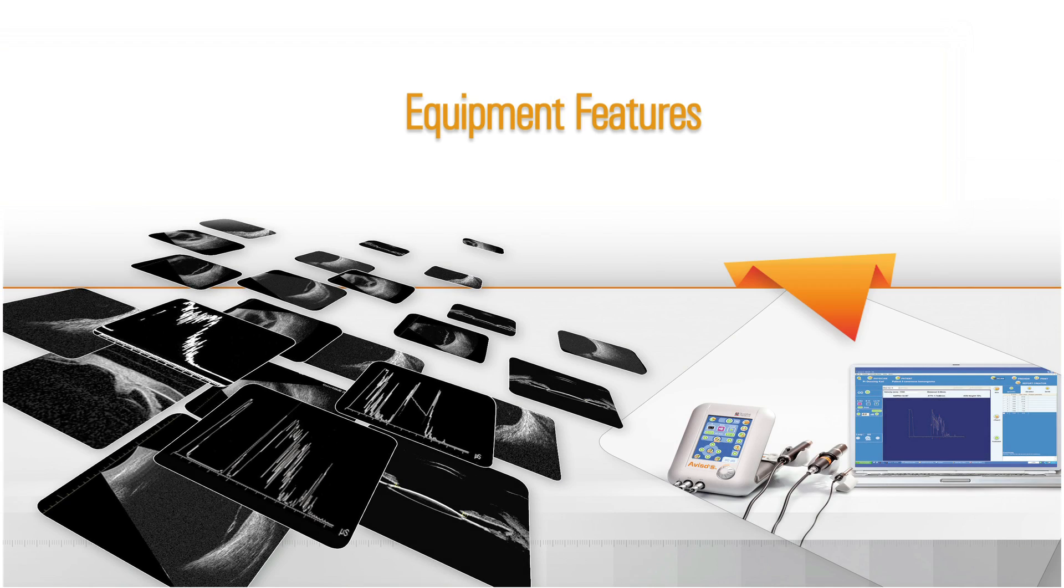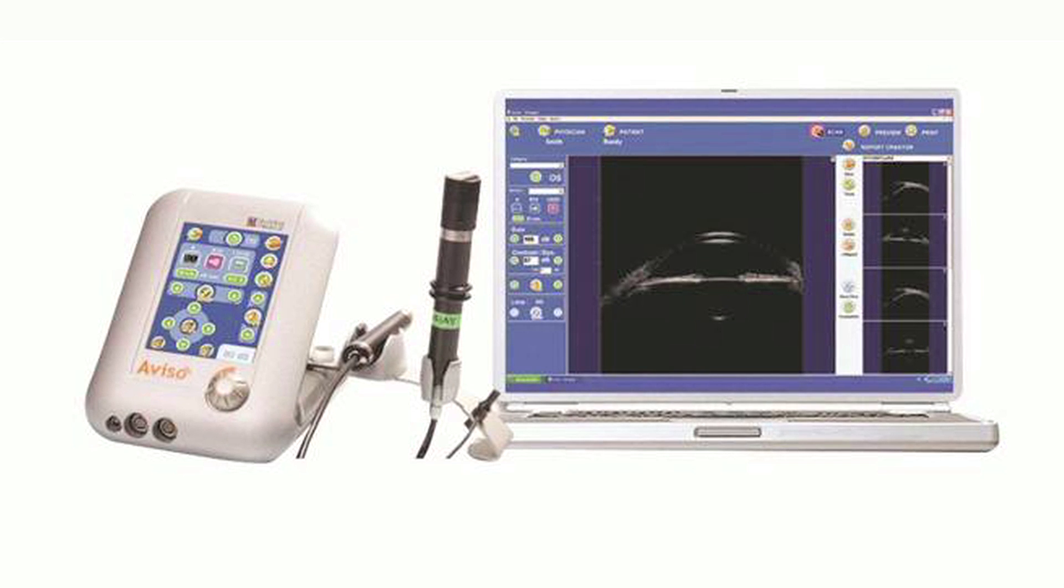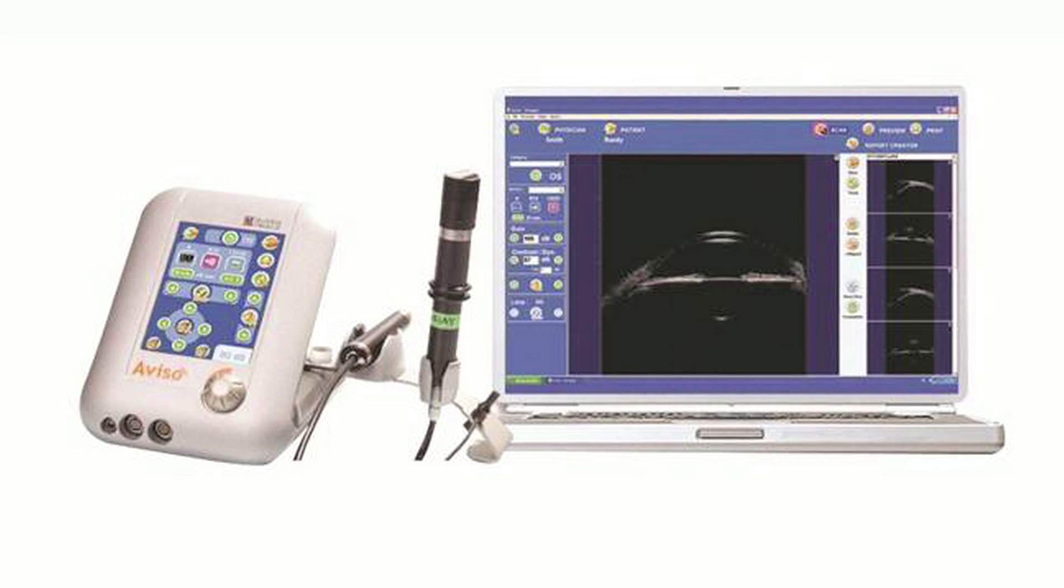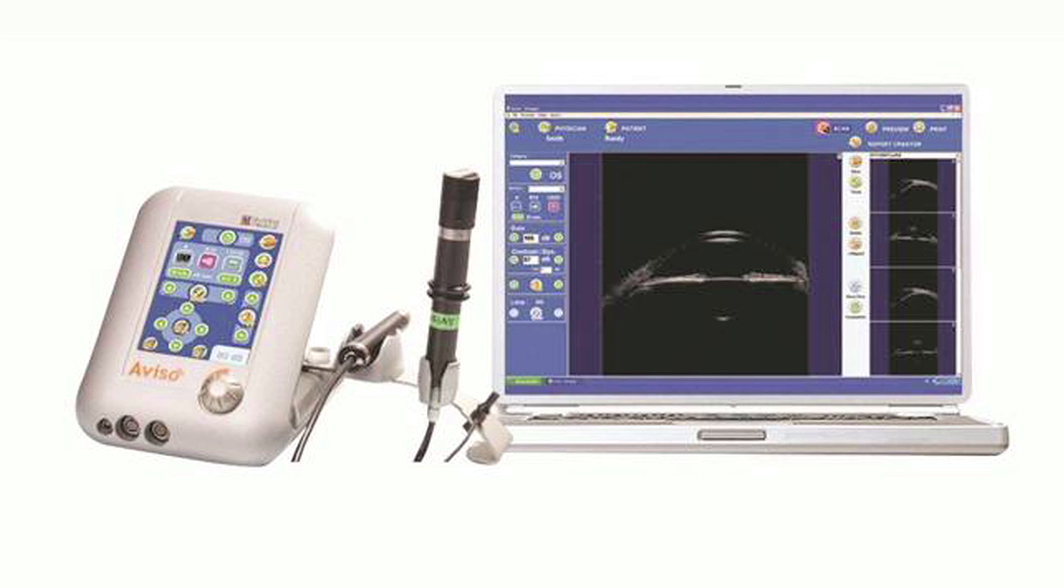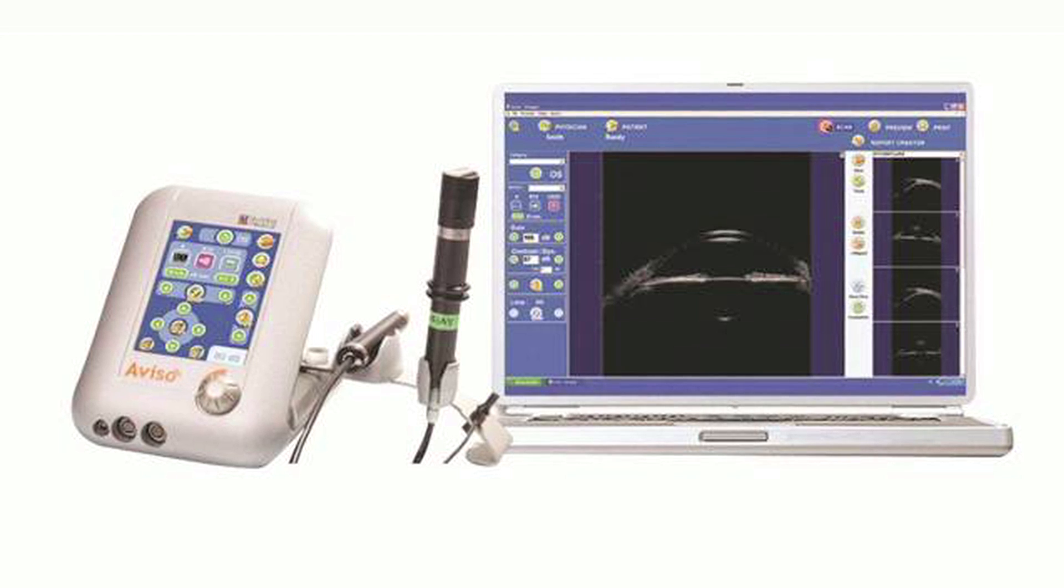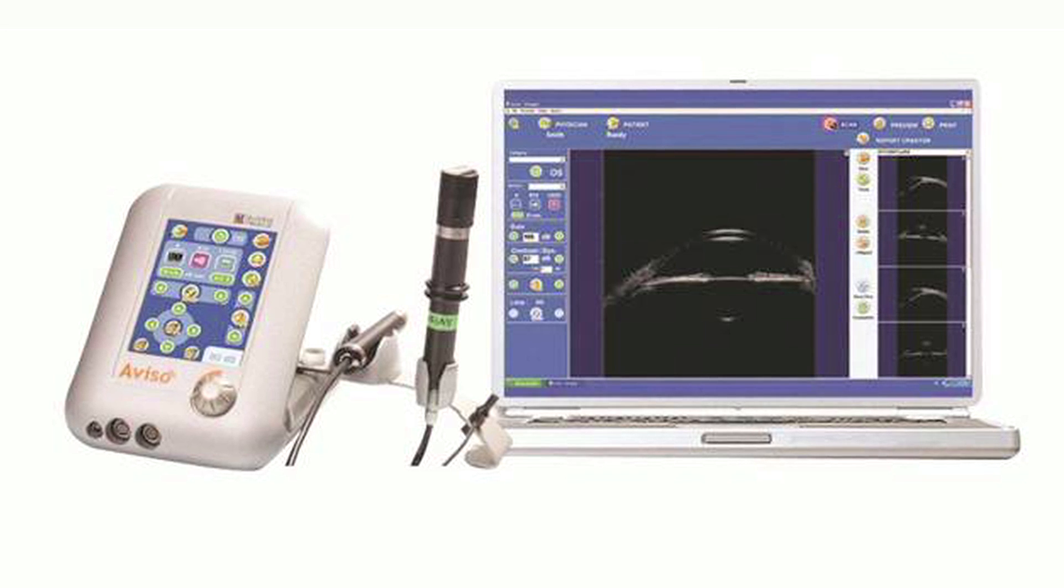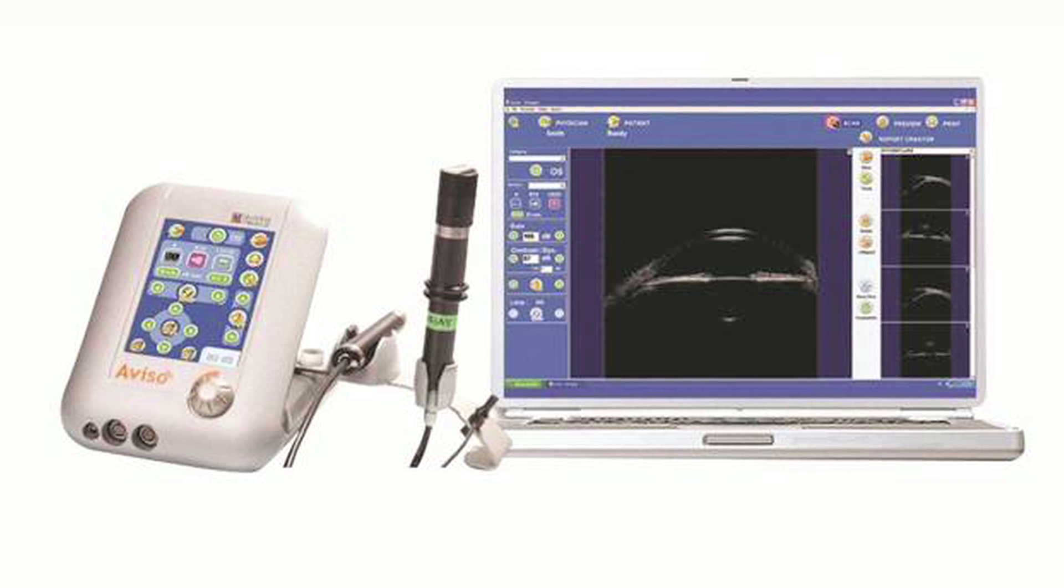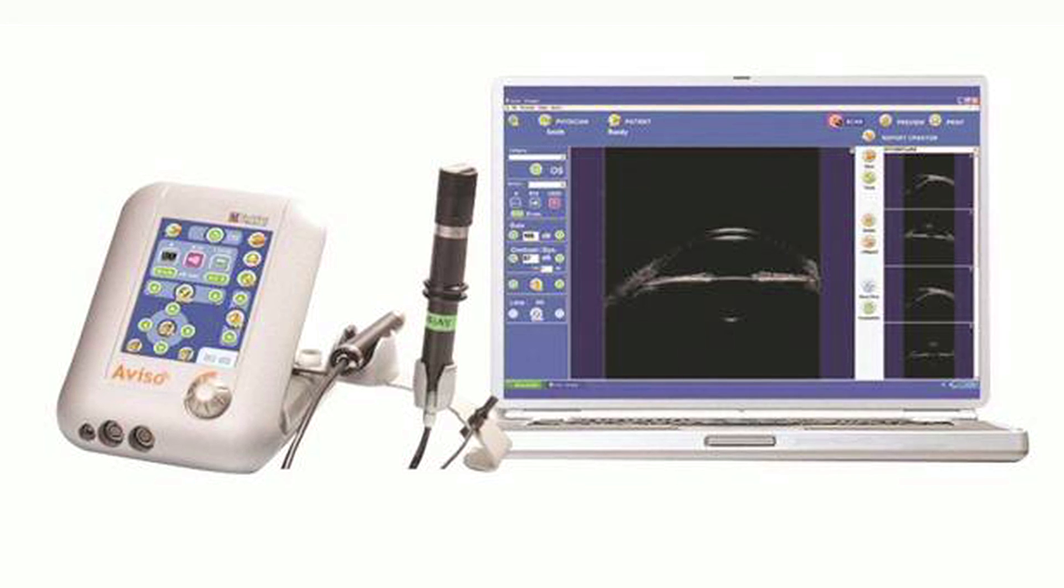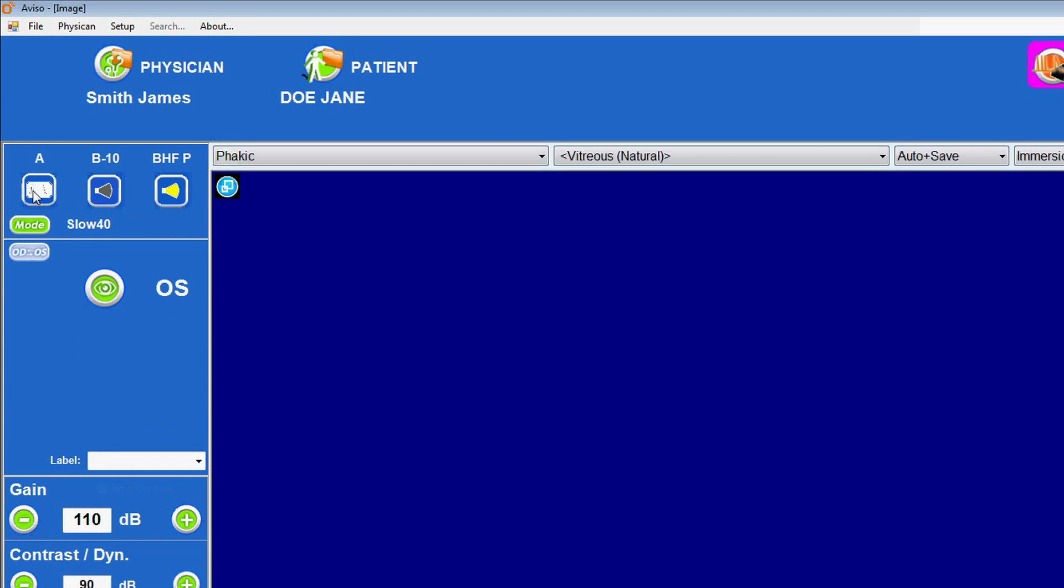Equipment features. We will now review some of the features and techniques for using Quantel Medical's Aviso ultrasound system to perform A-scan biometry. The Aviso is a modular ultrasound platform featuring a portable, compact main unit with a user-friendly touch screen connected to a laptop or desktop computer through a USB cable. Image acquisition can be controlled via the touch screen or the computer, where data and images are displayed. Press the biometry A icon to access biometry mode.